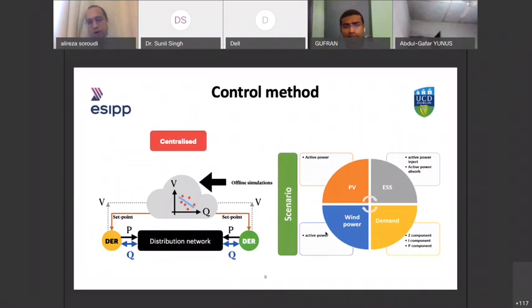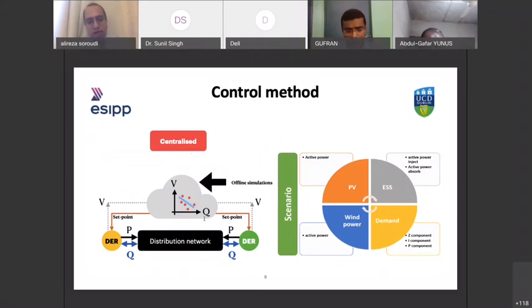There are two approaches for coordinating the action: a centralized one and a decentralized one. In a simple distribution network with two DERs exchanging active and reactive power with the grid, the question is how to tune the Q part. One way is to sense the voltage at the connection point, send it to a cloud, and use the VVC curves already stored there to find out how much Q should be injected or absorbed — with set points coming from a centralized server or distribution network operator.